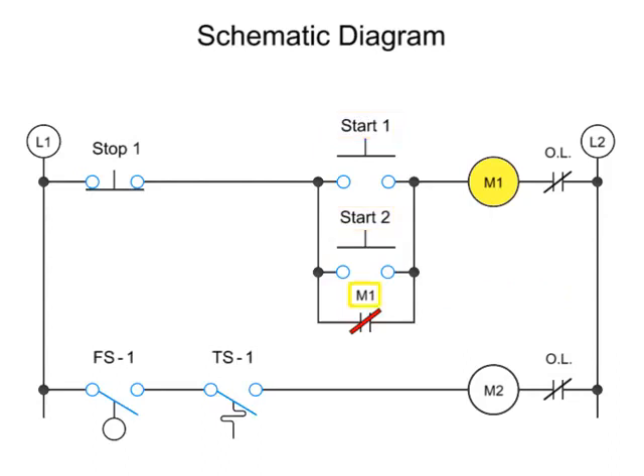There is also control logic associated with normally closed switches. NOT logic occurs when there is a single normally closed switch in a circuit. Thus, when the normally closed switch, stop 1, operated by a manual push button, is pressed, the M1 coil is shut off and the M1 holding contact is deactivated.